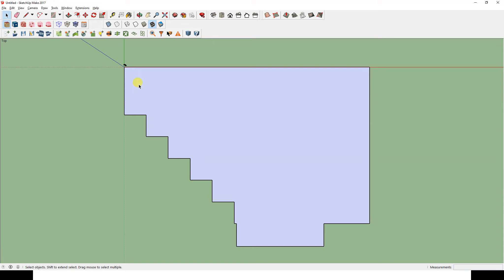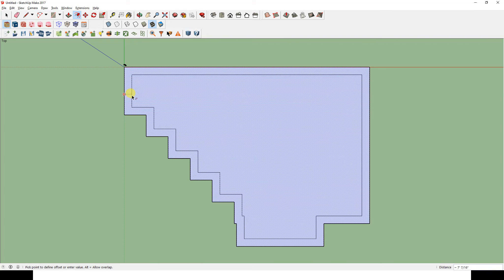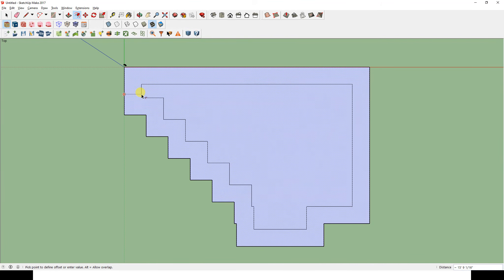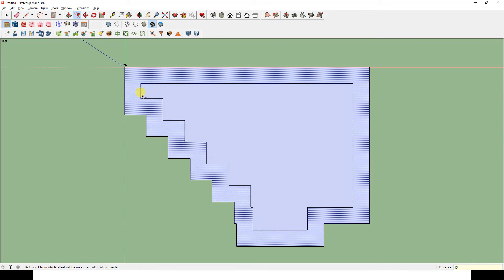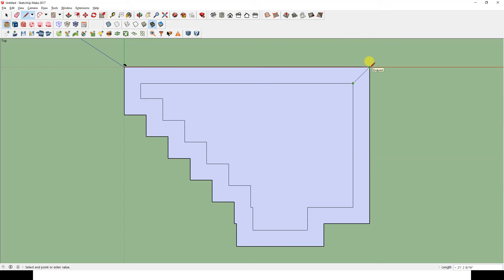We're going to come back to this floor layout in a second video, but sometimes if you have no layout at all, the simplest way is to start by making what's called a core and perimeter zoning plan. I'm going to go ahead and explode this group. A core and perimeter zoning plan basically assumes that the only information we have is to define a perimeter area — which is often about 15 feet from the edge — where we know that the thermal heat gains are different, lighting levels will be different, and they may have daylighting controls.